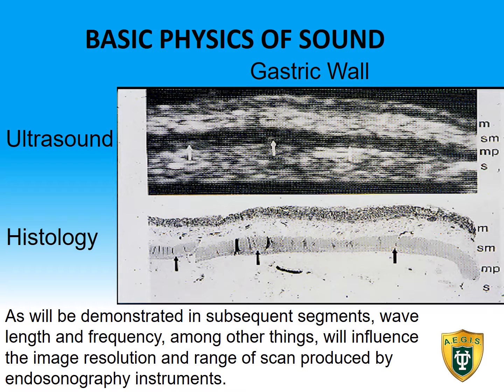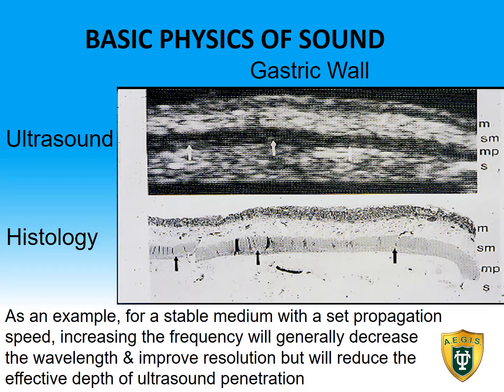As will be demonstrated in subsequent segments, wavelength and frequency, among other things, will influence the image resolution and range of scan produced by endosonography instruments. As an example, for a stable medium with a set propagation speed, increasing the frequency will generally decrease the wavelength and improve resolution, but will reduce the effective depth of ultrasound penetration.